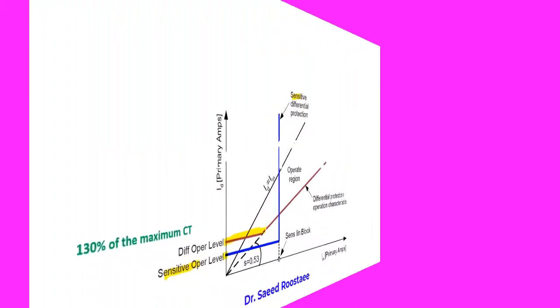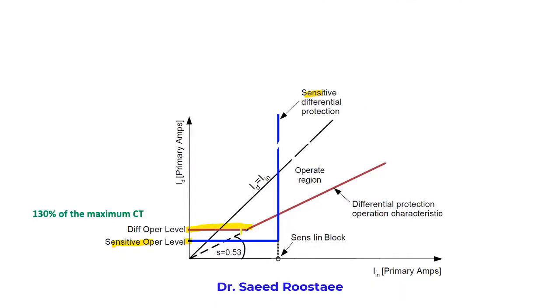The differential operating current should be set from 50% to 150% of the biggest CT, but we usually set to 130% of the maximum CT.